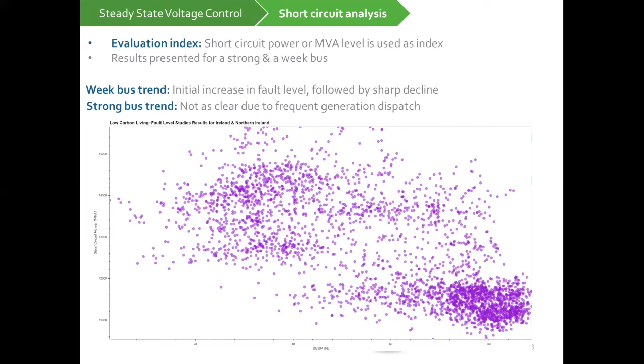For a strong bus, between 20 to 60% renewable penetration, if you see at the bottom, the trend is not as clear. This occurs because the bus being considered is in the proximity of a conventional unit. If the unit is dispatched, the fault level increases and vice versa. However, we can see a very clear clustering of fault level appearing at the bottom right corner of the screen at high renewable generation levels, whereby the conventional unit in question is less likely to be dispatched, and hence a scarcity can be seen to be appearing.